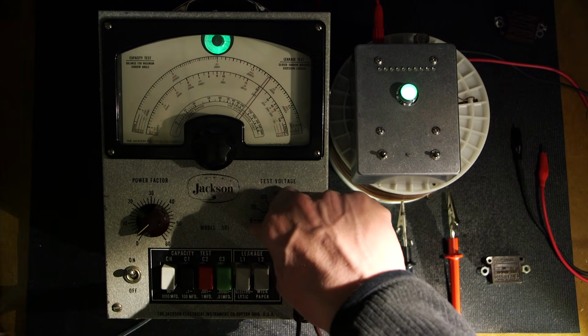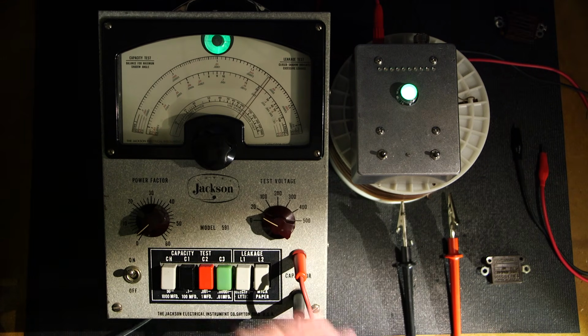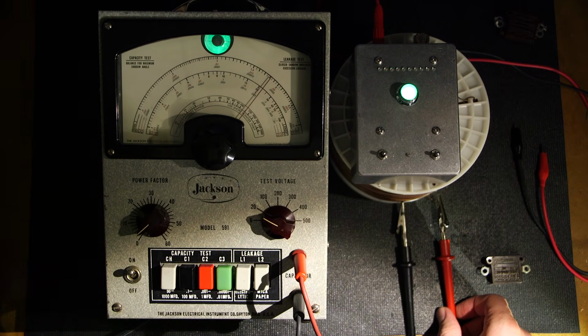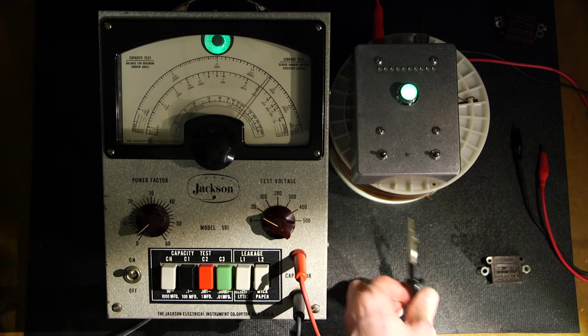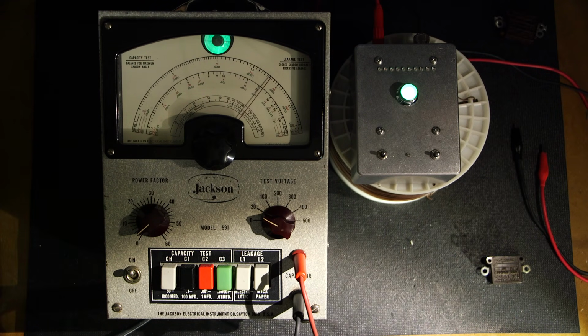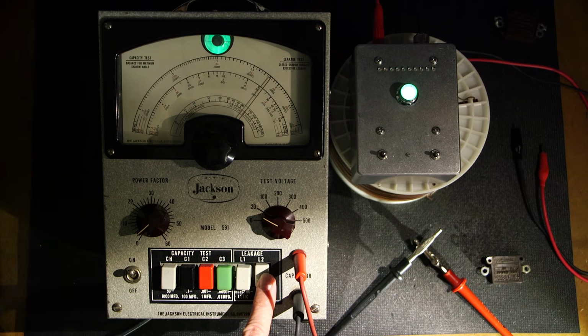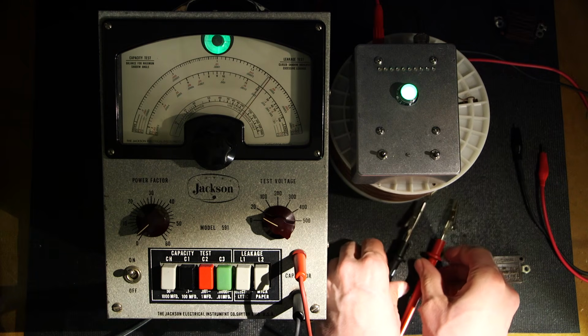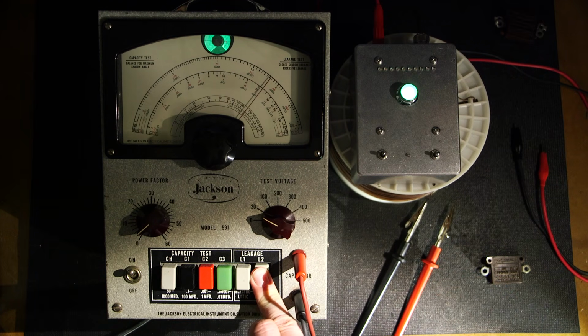So to give you an example, we'll set it to 20 volts. I wouldn't want to go much higher than that because the next step is 100 volts. What I'll do is short the two leads out here, and you'll see there's excessive leakage - the eye doesn't open. Whereas if I move these apart again, no problems.